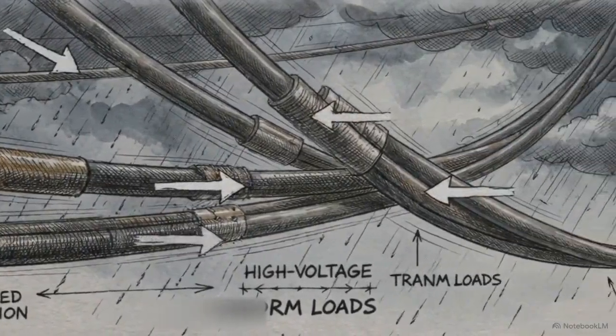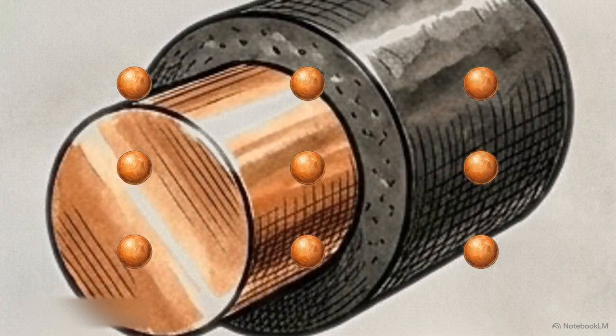A central power station generates electricity at thousands of volts, yet residential neighborhood requirements are much lower, typically 120 or 240 volts. Transporting energy between the station and the consumer requires pushing electrical current through miles of conductive wire. Every meter of that wire resists the flow of electrons. This is the math of joule heating.